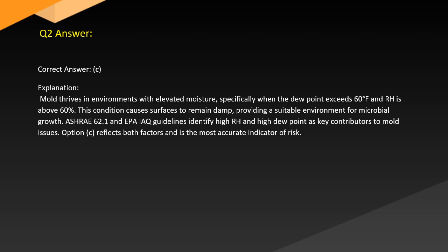Answer. Correct answer, C. Explanation. Mold thrives in environments with elevated moisture, specifically when the dew point exceeds 60 degrees and RH is above 60%. This condition causes surfaces to remain damp, providing a suitable environment for microbial growth. ASHRAE 62.1 and EPA guidelines identify high RH and high dew point as key contributors to mold issues. Option C reflects both factors and is the most accurate indicator of risk.